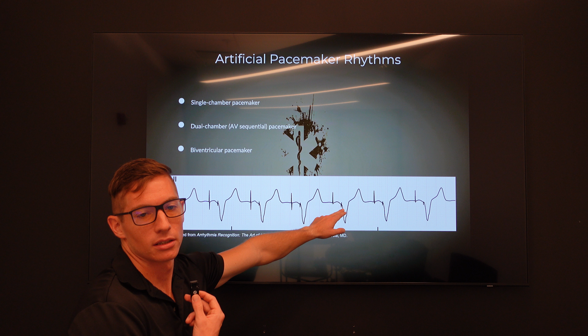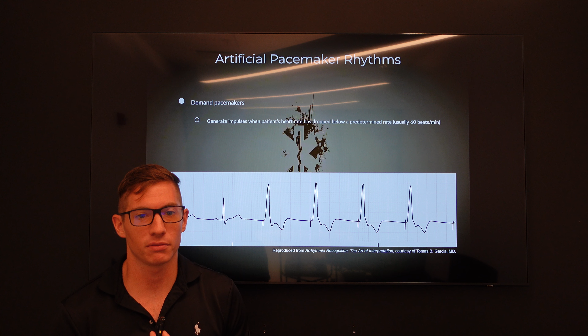There are two types of rates. You have fixed rate pacemakers, seldom used today, which generate a pacing impulse at a pre-programmed rate. And then you have demand pacemakers, equipped with a sensor that generates a paced impulse when the patient's heart rate drops below a predetermined rate, usually 60 beats per minute. So the demand pacemaker is more of a fail-safe, and the fixed rate pacemaker is more of this is what is going to run you from now on.